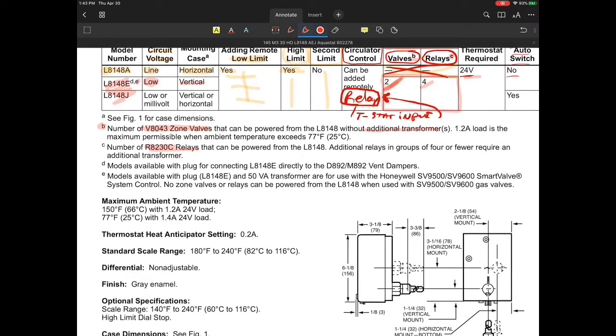And then obviously there are some models I talked about earlier that can control a zone valve and things like that that you have to do on there. There is one other thing that I want to point out too, this item E. So the note E, they talk about models available with that plug, the L8148E. That is a 50 VA transformer. They're used with these Honeywell SV9500 smart valve systems.